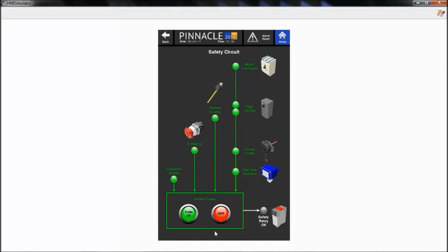So if we circle around the dryer and we find the E-stop that's pressed in and pull it out, we'll see that we now have the control power illuminated, and either directly from this page we could latch control power or from the control page. Notice when the control power is off, our safety relay OK button is not illuminated. Once we turn on control power, we get a green indicator that the safety relay has been latched.